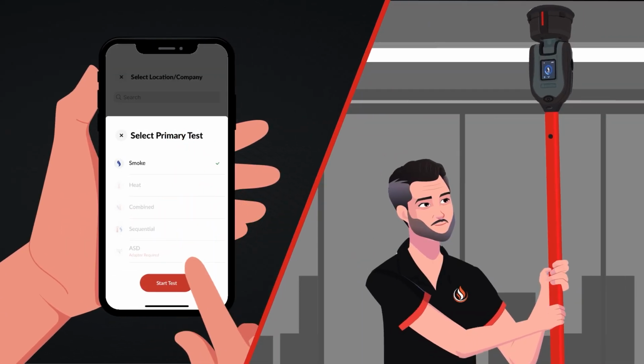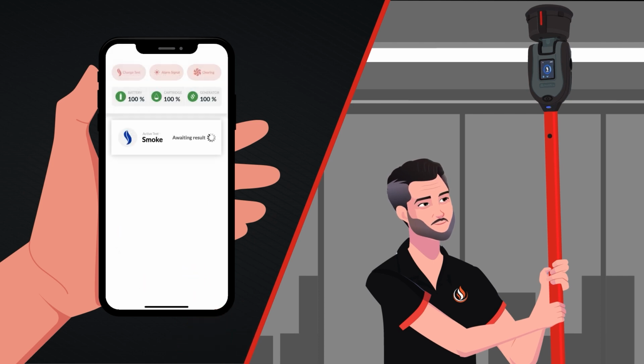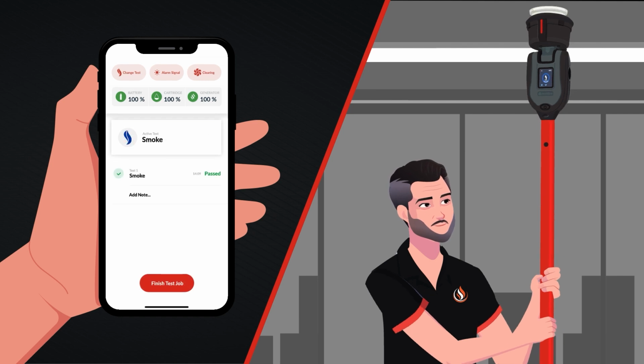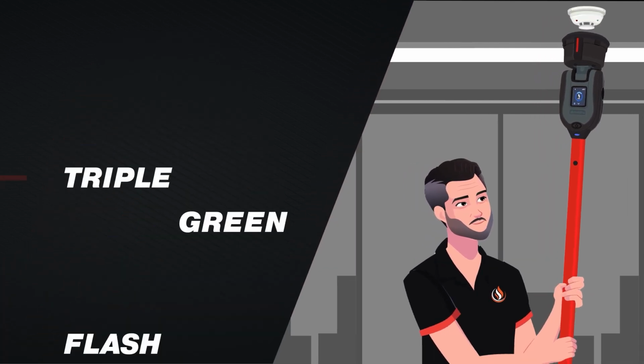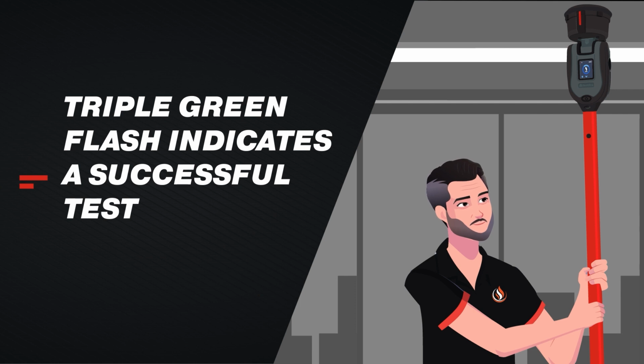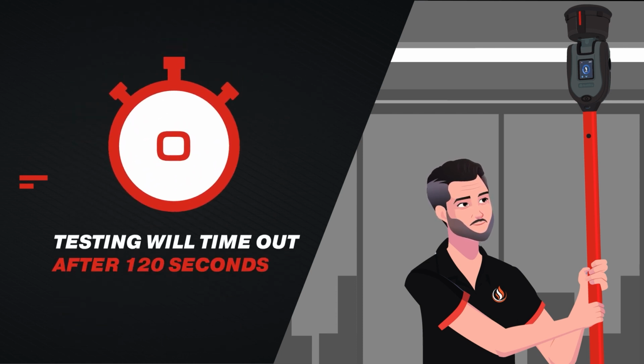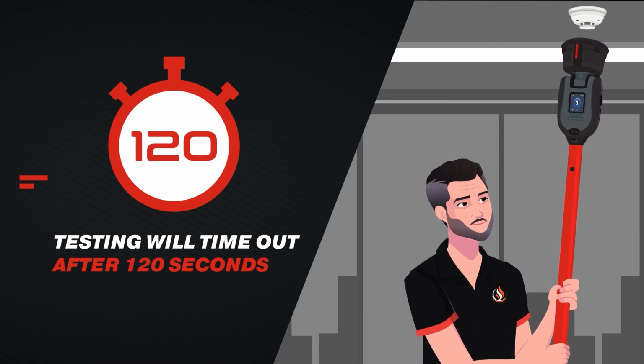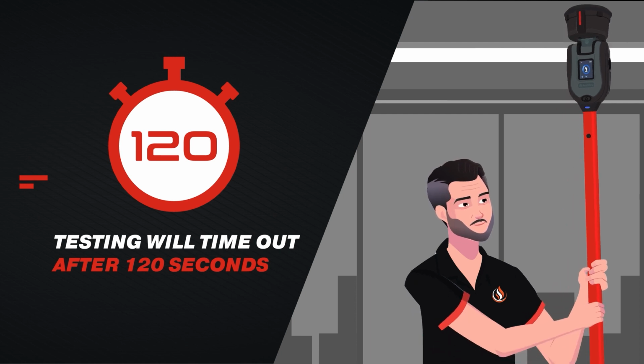Next, select the type of test you want to carry out and raise Testifire XTR2 so the detector sits within the test cup. The LEDs will triple flash green to indicate a successful test, which will be recorded as a pass in the app. Triple red flashing LEDs indicate that the detector was not activated within 120 seconds and will be recorded as a failed test. Note it is mandatory for additional notes to be added against a failed detector.